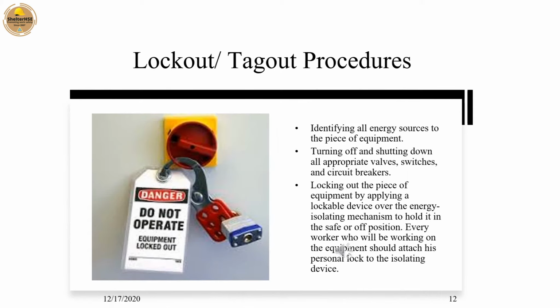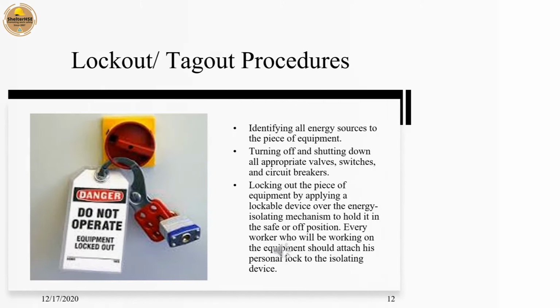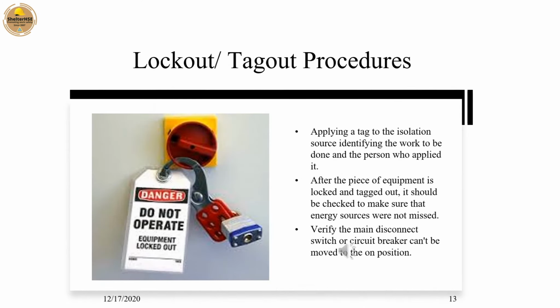Identifying all energy sources to the piece of equipment. Turning off and shutting down all appropriate valves, switches, and circuit breakers. Locking out the piece of equipment by applying a lockable device over the energy isolating mechanism to hold it in the safe or off position. Every worker who will be working on the equipment should attach his personal lock to the isolating device. Applying a tag to the isolation source identifying the work to be done and the person who applied it.